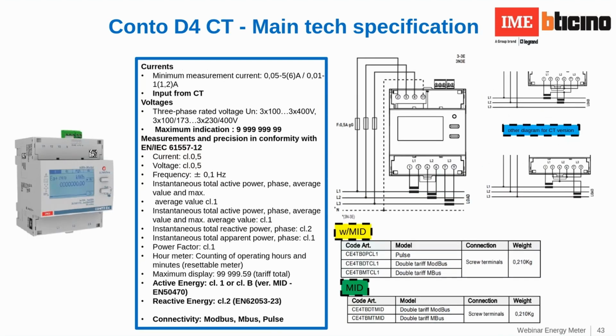Okay, this is the Conto D4 3-phase with current transformer insertion, so the indirect connection. Here also we have the maximum indication in 9 digits, but the difference with the direct model is that the number of the decimal part in the energy value depends on the current transformer ratio. In fact, in case of direct connection, you have 2 decimal points and 7 for the unit part. Also here in the upper part, you find the connector for the connectivity for the Modbus or MBus protocols.